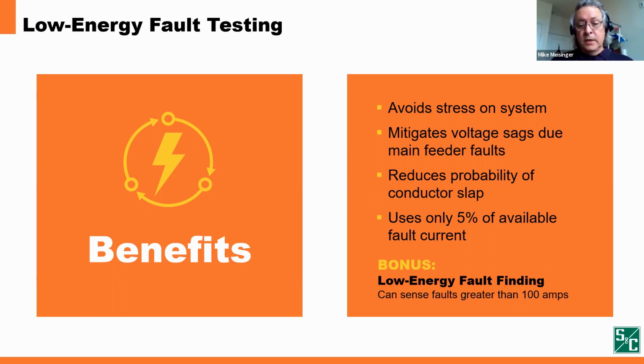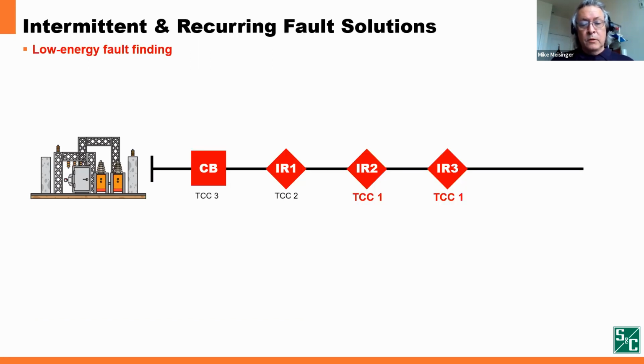And we've recently introduced a lower fault finding threshold for weak systems or feeders that are very long in length. And we can now detect faults down to approximately 100 amps. Next slide, please. So there's two benefits, but before we get into the benefits of the recurring faults or the highly resistive faults, I wanted to introduce a concept we call low energy fault finding. And as in Clever's one line before, we have the circuit breaker CB, IR1, IR2, and IR3.